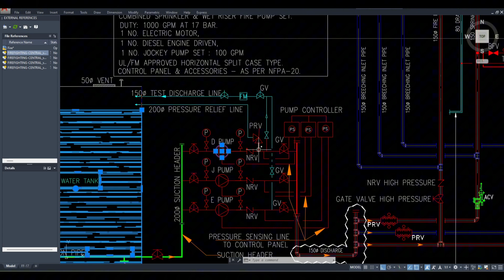So that's why it will have a pressure relief line, coupled with the PRV valve, and it goes back to the system. It delivers whatever water is required into the system, and the rest of the water goes back to the tank. So for a generator diesel pump line, it should always connect with a pressure relief line. If this is missing, you need to check whether it's missing and whether they have considered it or not.